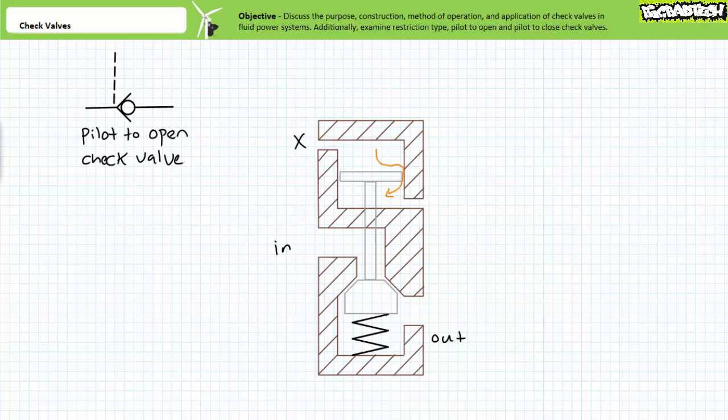Given liquid is considered incompressible, any liquid that leaks past the pilot piston would obstruct its continued movement. For this reason, the vent or drain port on the rod end of the pilot piston ensures any liquid leaking past the pilot piston is drained away.